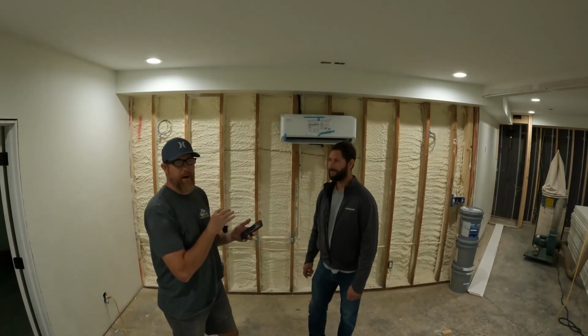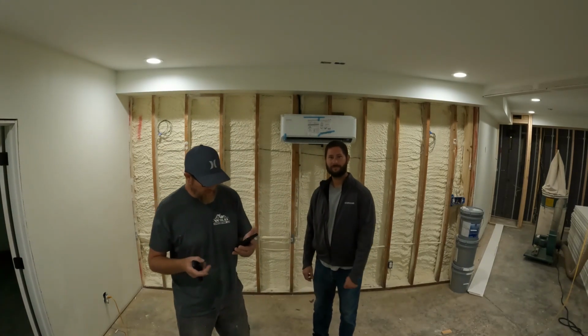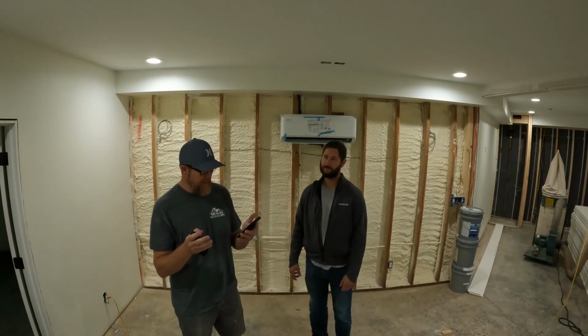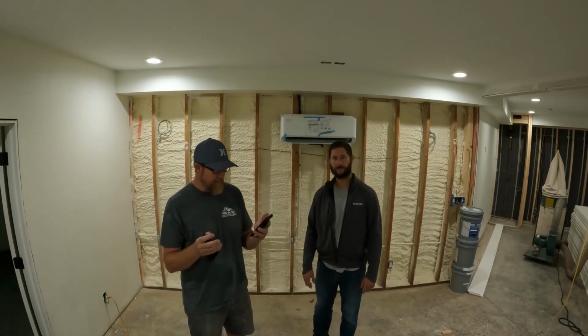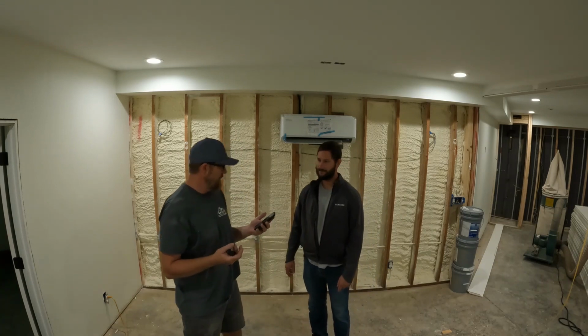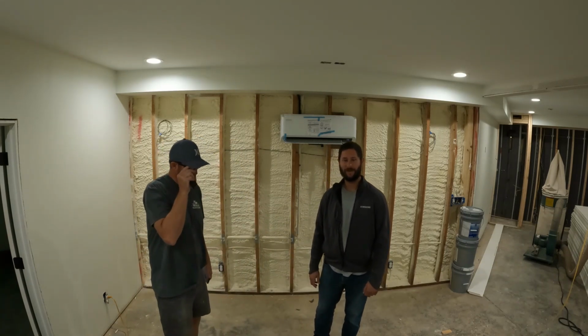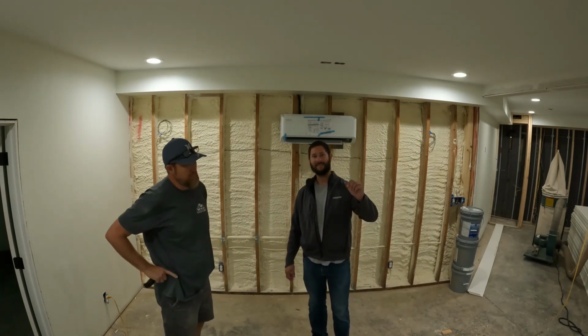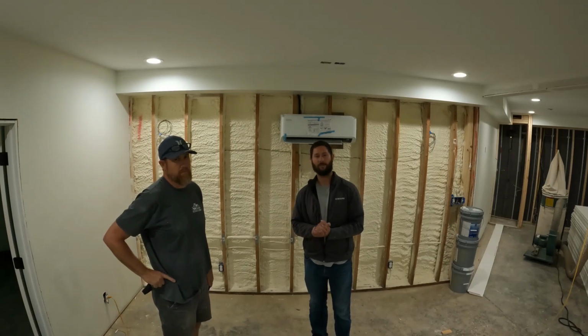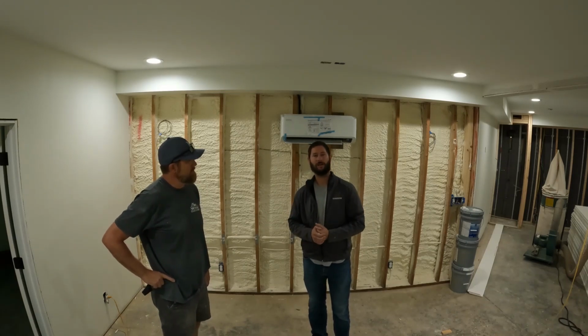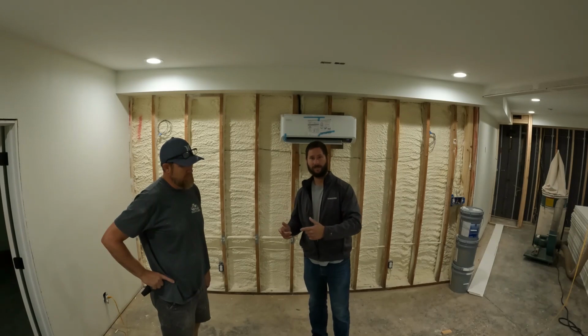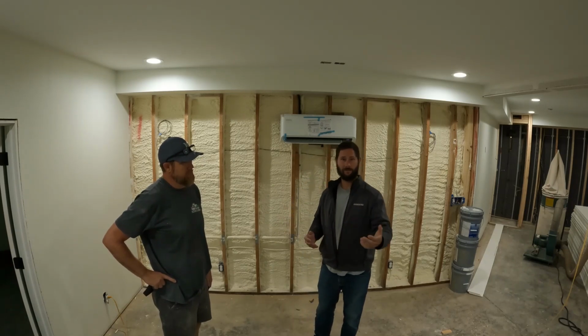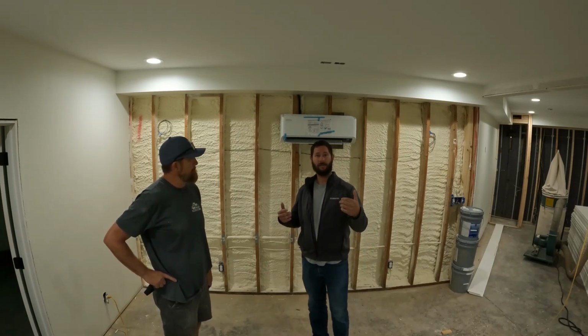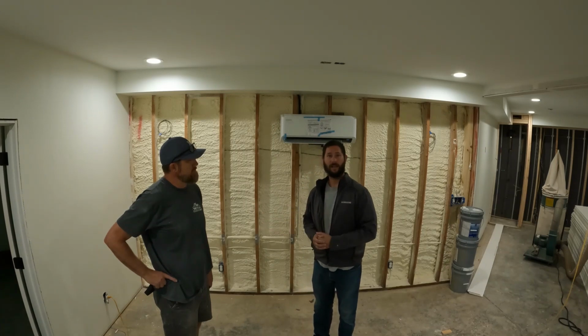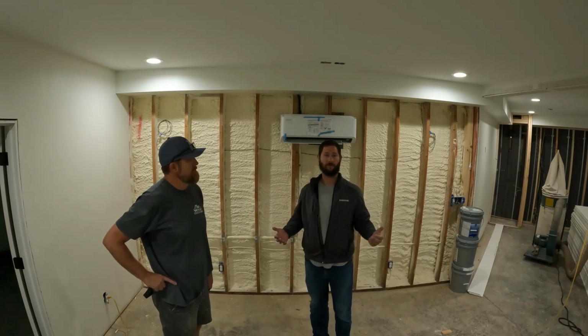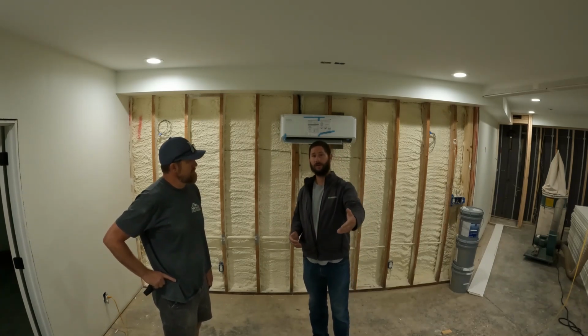All right, you see the foam. So how beneficial is the foam for this type unit, and does it have an impact on the sizing of the unit? Absolutely. So the sizing definitely changes the sizing because, of course, like I said before, I use a square foot per ton sizing. So where we would be 500 or 600 square foot per ton, just standard, now with foam, it's 1,000 square foot per ton. So we're cutting our load in half.